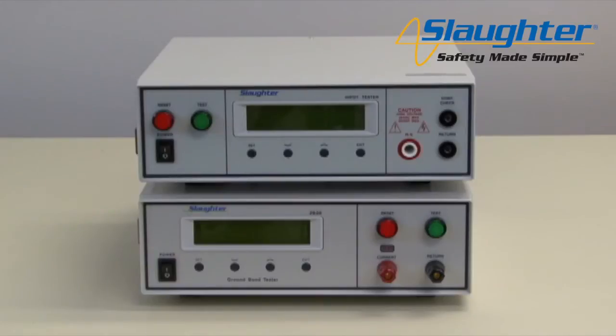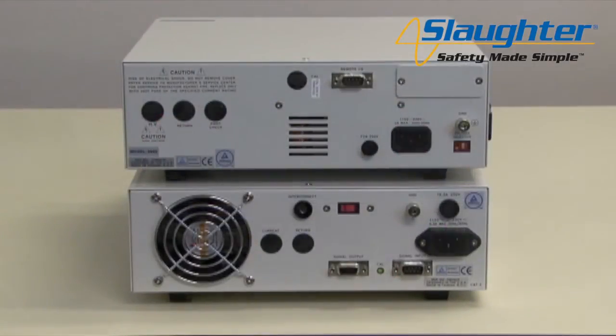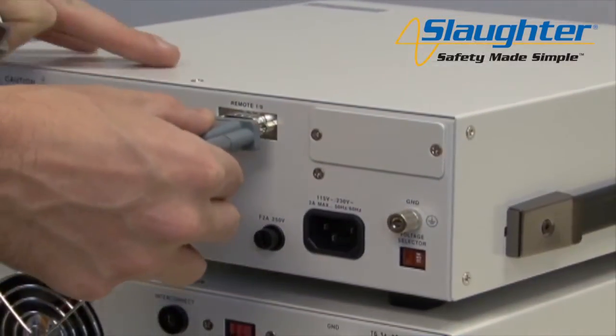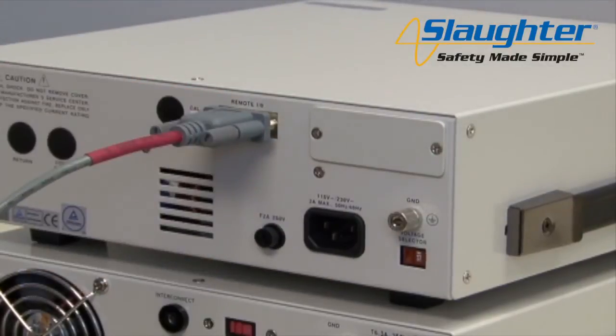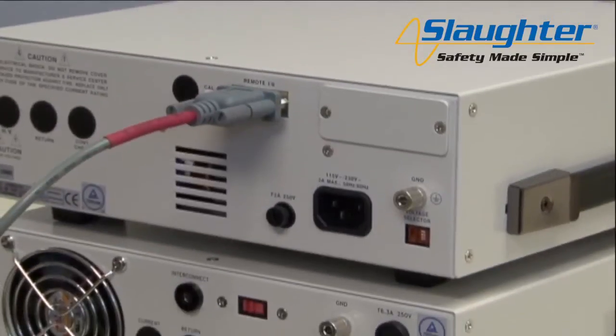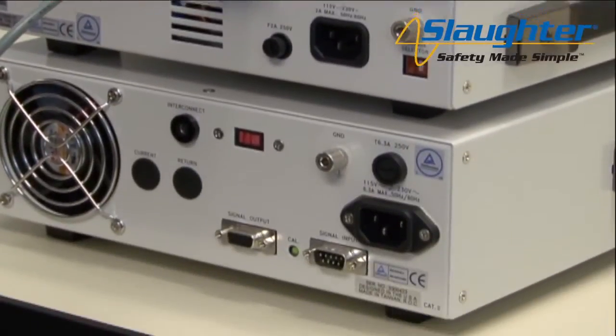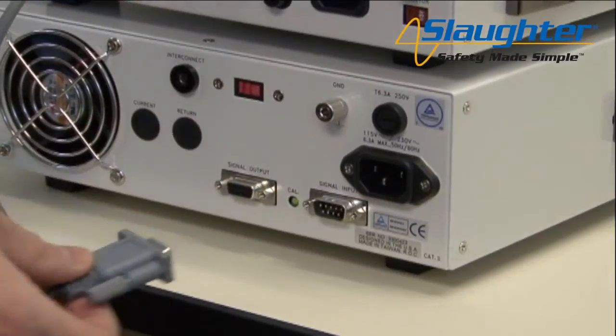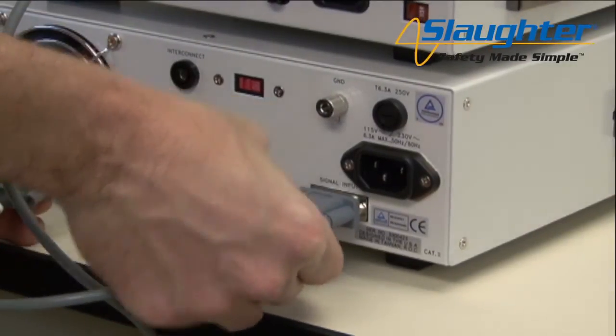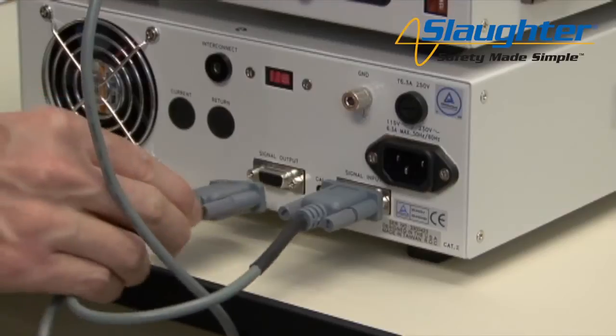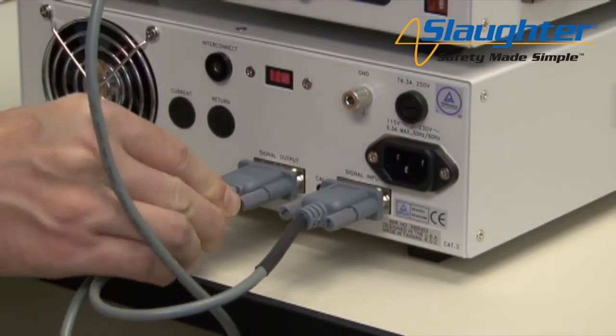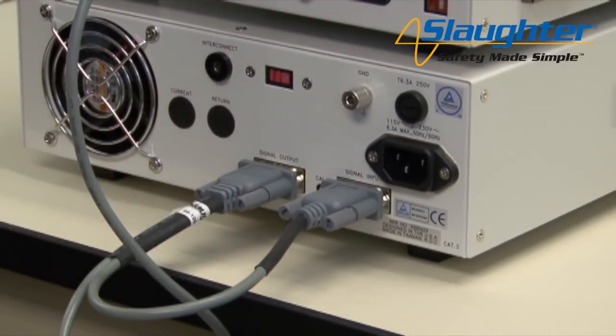Before making any connections, make sure both of your testers are turned off to avoid a potential shock hazard. Using the interconnection cable set, connect the red cable end labeled Hipot to the remote input-output of the 2900 tester. Next, connect the black female cable end to the signal input of the 2600. Then connect the black male cable end to the signal output of the 2600. These connections will allow two instruments to share signals so they can operate as a system.